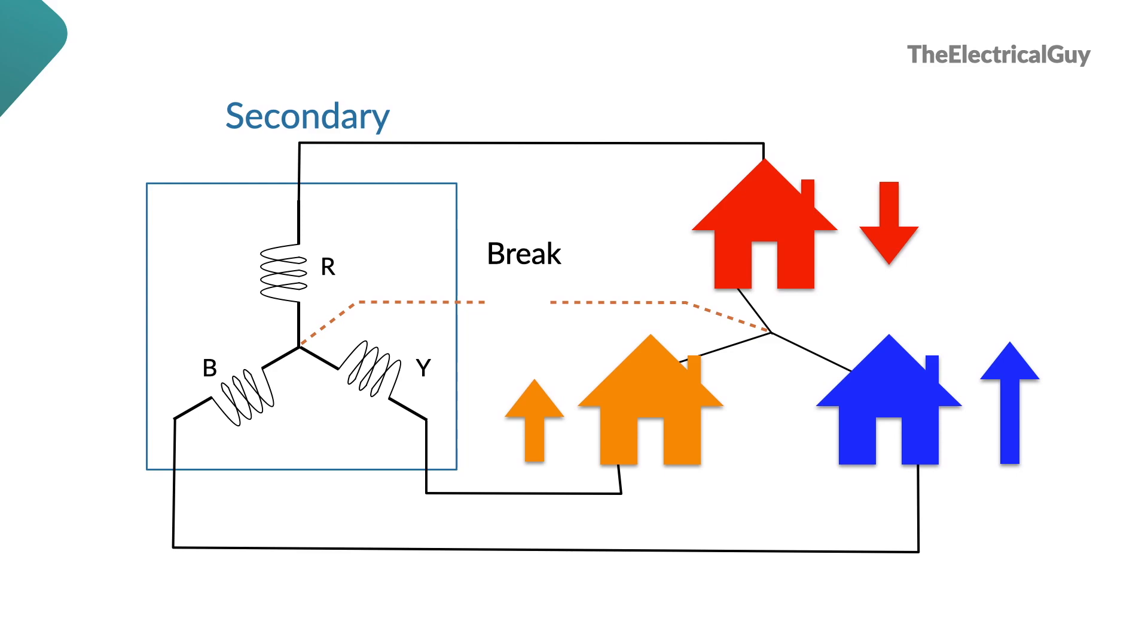Hence, this situation is called floating neutral, or some people also call it floating ground. Floating neutral doesn't mean that the neutral wire floats in air. As the value of potential of such open neutral keeps changing or keeps floating based on the load, it is called floating neutral or floating ground. I'll also show you floating neutral in our simulation in a few minutes, and that's very interesting.